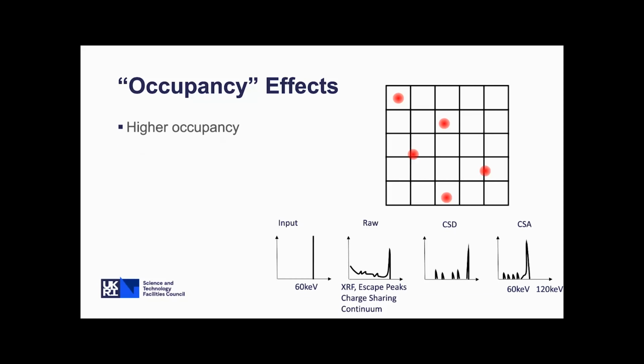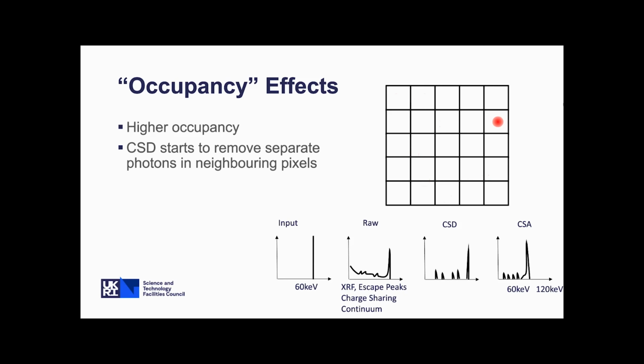If we get to higher occupancies, so if we throw more X-rays into our frame, it gets increasingly difficult to do the charge sharing corrections. When we now do the charge sharing discrimination, we start to see individual photons in neighboring pixels, and we'll throw these away even though they were separate events. We've got no way of knowing if they were charge sharing or separate photons. So even though we're at too high a flux, we'd actually get no data from that. With charge sharing discrimination, if you see that your flux is going down when you're turning the wick up on your source, then you're probably in a scenario where the charge sharing discrimination is artificially throwing away events.